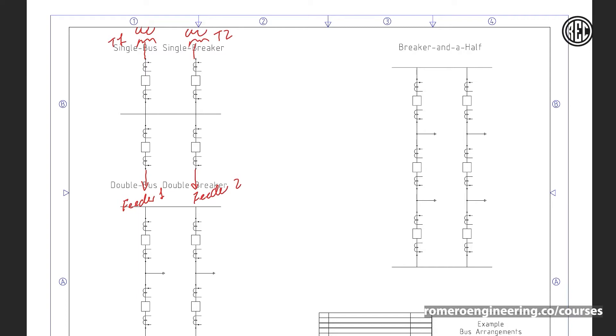The downside to this configuration is that if we have a fault on the bus, we have to clear all the breakers connected to that bus, interrupting service to all feeders. In this example, to isolate the fault we need to trip all four breakers — for both transformers and both feeders — interrupting service to feeder one and feeder two. So this is a simple design, but very limiting: there is no redundancy, and a bus fault will interrupt everything fed from that bus. The upside is that it's the most economical option.